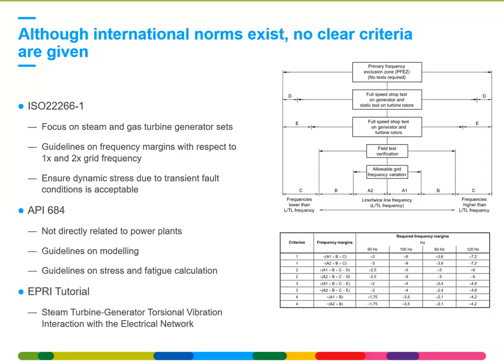The standards do not give clear criteria on these phenomena, so the only focus is on the guidelines on frequency margins with respect to once and twice grid frequency. So a table is given, as you can see on the right, which recommends exclusion zones from these excitation frequencies. So any time when a disturbance occurs, a short circuit, an imbalance on the grid, you will excite the machine at once and twice grid frequency. So in order to avoid resonance, the norm stipulates these exclusion zones. The idea is to ensure that the dynamic stress due to a transient fault is acceptable.